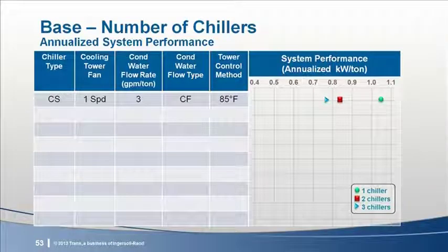The base case is a constant speed chiller, single speed tower fan, condenser water design flow rate of 3 GPM per ton, a constant speed condenser water pump per chiller, and a tower control to maintain 85 degrees. For this system, we analyzed performance with 1, 2, or 3 chillers. The annual kW per ton was drastically reduced with more chillers, but the difference from 1 to 2 was significantly greater than from 2 to 3.